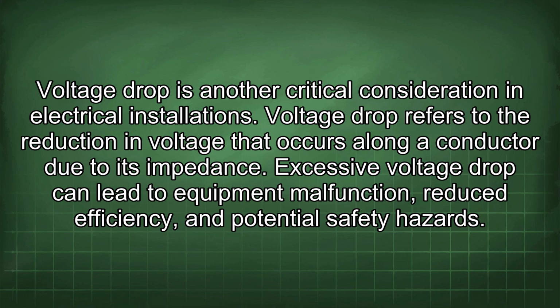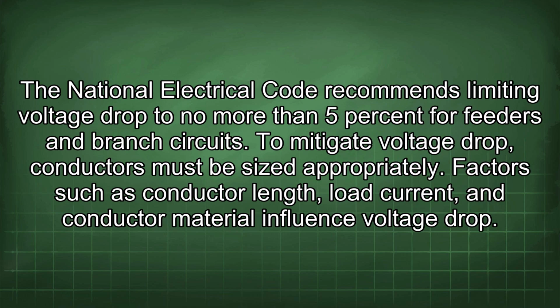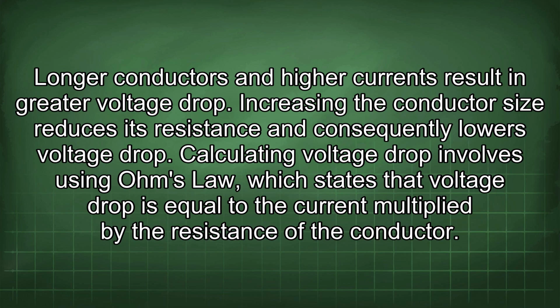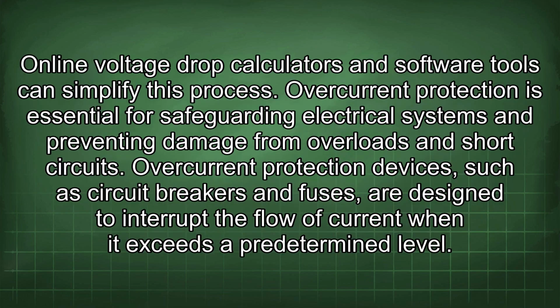Voltage drop is another critical consideration in electrical installations. Voltage drop refers to the reduction in voltage that occurs along a conductor due to its impedance. Excessive voltage drop can lead to equipment malfunction, reduced efficiency, and potential safety hazards. The National Electrical Code recommends limiting voltage drop to no more than 5% for feeders and branch circuits. To mitigate voltage drop, conductors must be sized appropriately. Factors such as conductor length, load current, and conductor material influence voltage drop. Longer conductors and higher currents result in greater voltage drop. Increasing the conductor size reduces its resistance and consequently lowers voltage drop. Calculating voltage drop involves using Ohm's law, which states that voltage drop is equal to the current multiplied by the resistance of the conductor. Online voltage drop calculators and software tools can simplify this process.